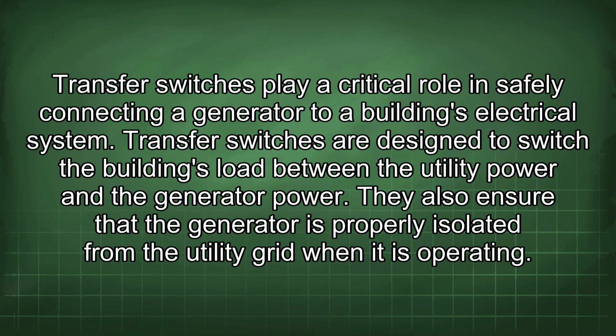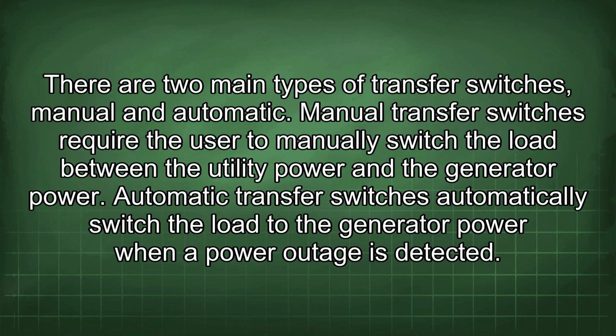Transfer switches play a critical role in safely connecting a generator to a building's electrical system. Transfer switches are designed to switch the building's load between the utility power and the generator power. They also ensure that the generator is properly isolated from the utility grid when it is operating. There are two main types of transfer switches: manual and automatic. Manual transfer switches require the user to manually switch the load between the utility power and the generator power. Automatic transfer switches automatically switch the load to the generator power when a power outage is detected.